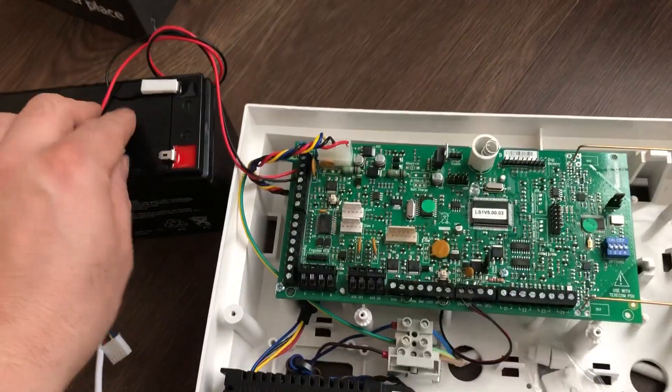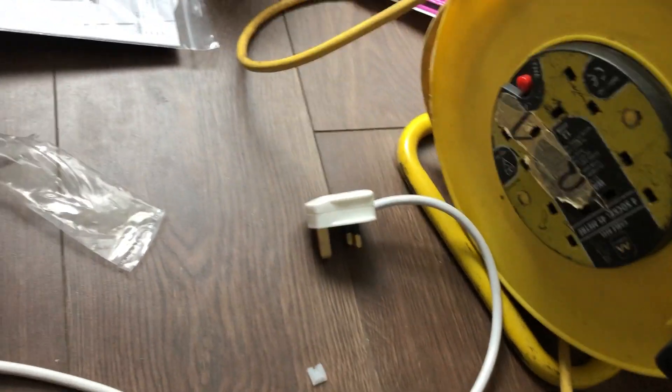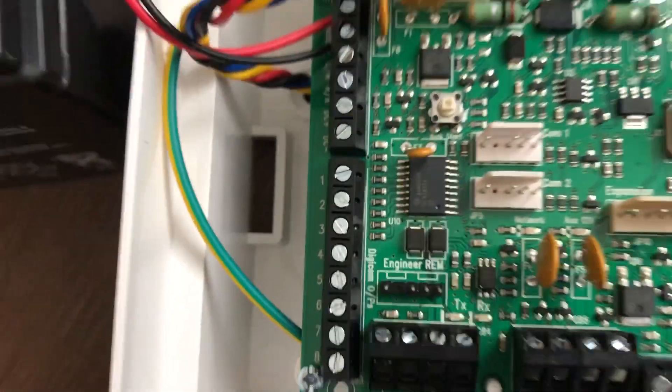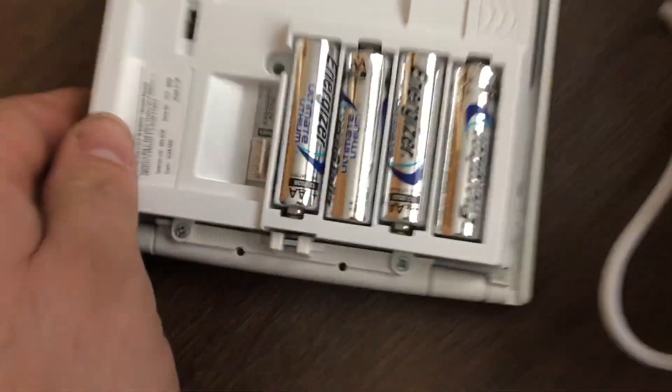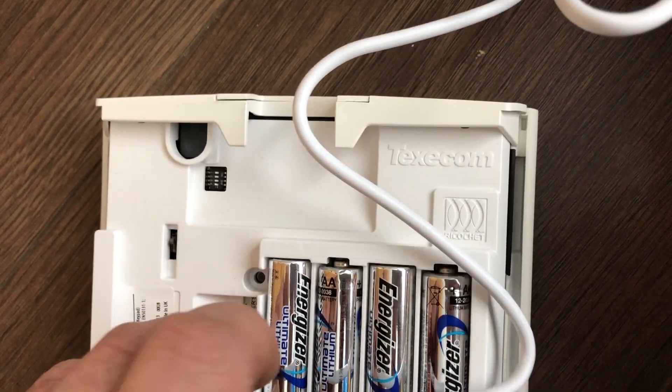I have my battery ready to go, just the red terminal disconnected and I'm wired into the mains ready. For the purpose of the video I'll be using a plug, whereas your system should be wired into a fused spur. First thing we need to do is take the engineer's lead and with the red wire to the left, find and locate the engineer's keypad port and plug it in. On the back of the keypad you'll see the other engineer's port, this time with the red lead at the top, and that's ready to go.